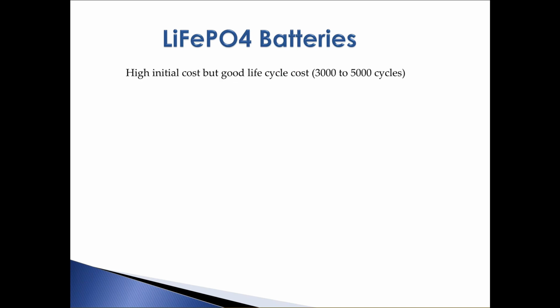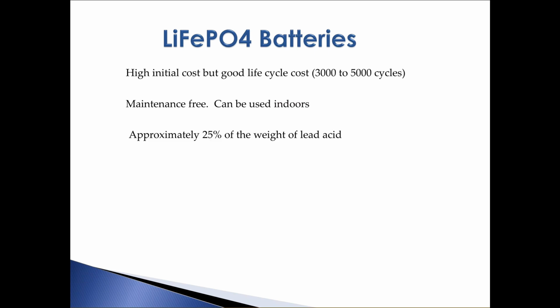They have a high initial cost, but they have a really good life cycle cost, and they're good for 3,000 to 5,000 cycles. It'll be the highest of any battery technology you can get for life cycle. They are maintenance free to the point you can actually use them indoors. They aren't going to outgas or have any other problems. They do weigh about 25% of the weight of the equivalent lead acid battery for the same usable capacity.